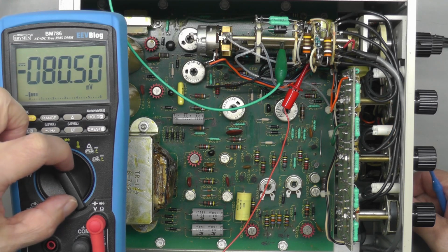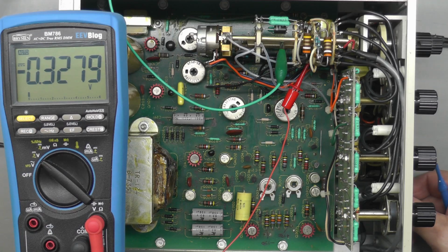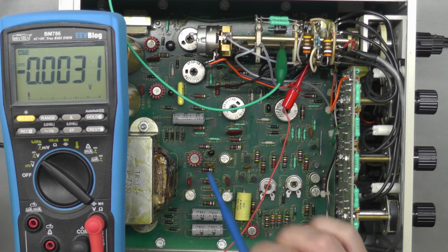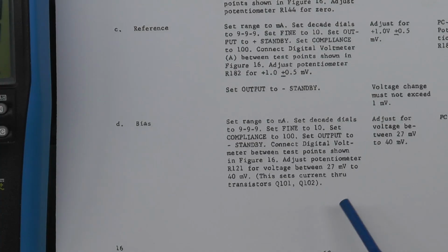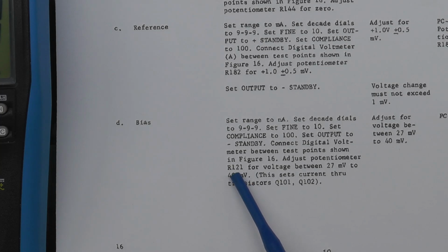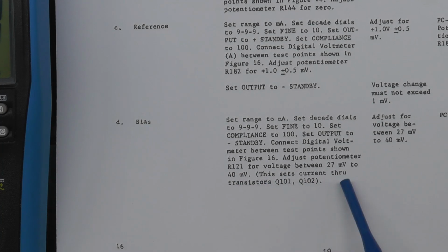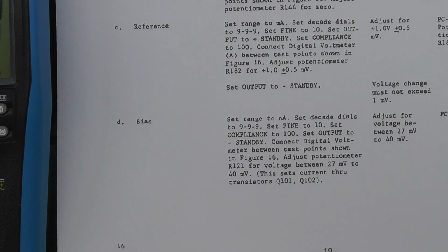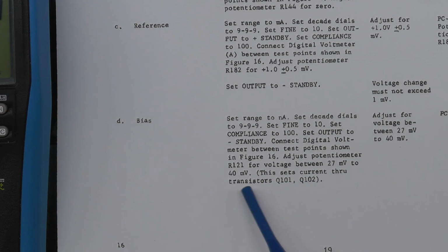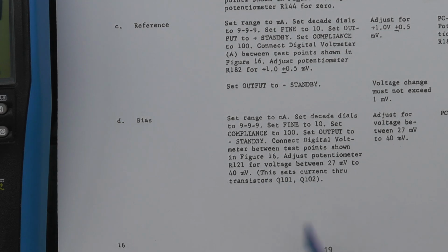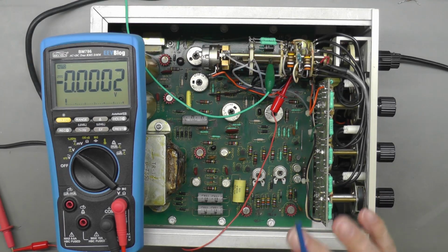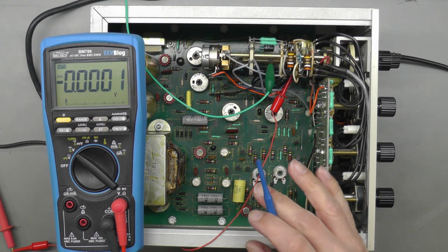Oh, we've got an overload, so let me just put it down to volts and try that again. And as you can see, minus 4.6 volts. That is miles off, and there's no amount of adjustment on that potentiometer which is going to fix that. You're supposed to adjust R121 for the voltage to be set between 27 and 40 millivolts, which sets the current through transistors Q101 and Q102. So clearly there's still a problem with the unit.